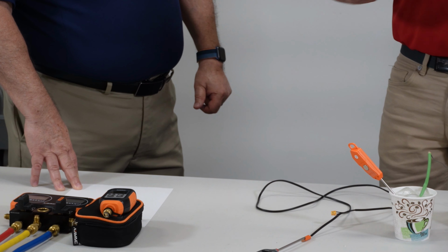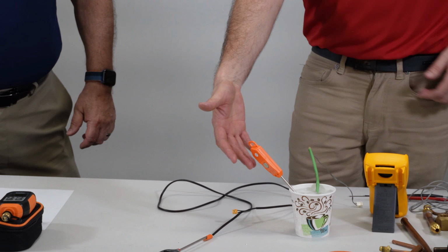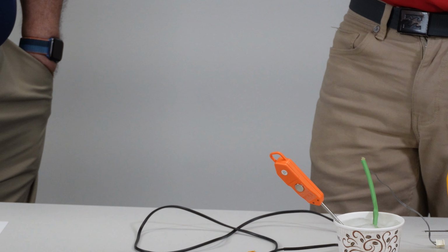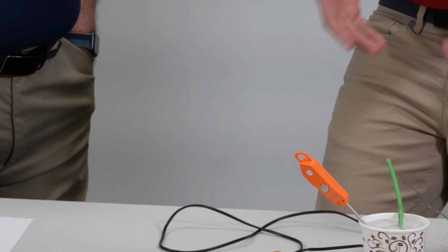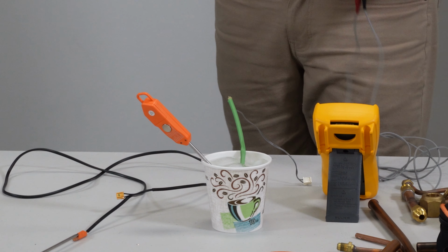So now you have a prop here showing how to measure or to reference the temperature of the thermistor. Correct. So we have two things we can do here in this example. We have a cup with ice water. Make sure, again, a cup of ice with water, and we stick the probe right into it. And then our temperature, just making sure that we're reading roughly 32 degrees. Correct. And then from there, what we can do is we can connect our meters and our needles.